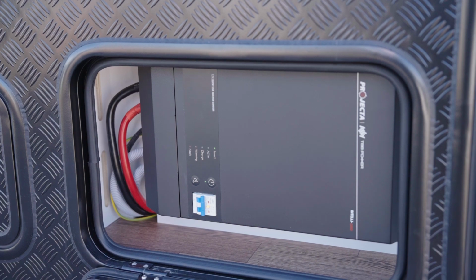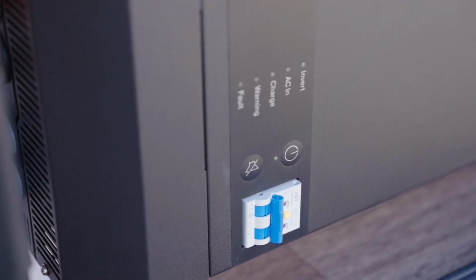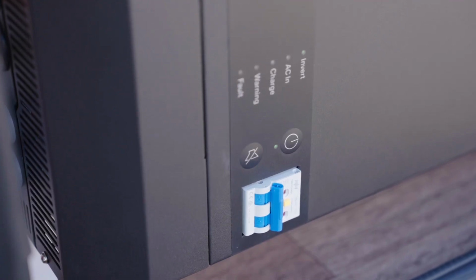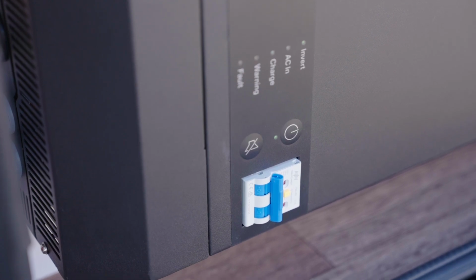Now, one switch you won't find up here, because it's actually located directly on the inverter charger, is a discrete residual current circuit breaker with overcurrent protection known as an RCBO. It's integrated directly into the inverter charger and ensures maximum protection for you and your equipment. It's fitted with the overcurrent feature, which will also protect your wiring system. If this trips out, it will need to be reset manually with a simple flick of the switch.